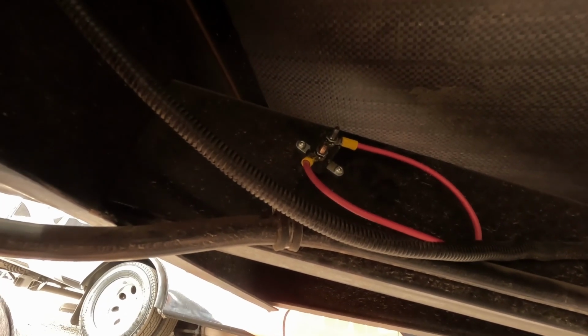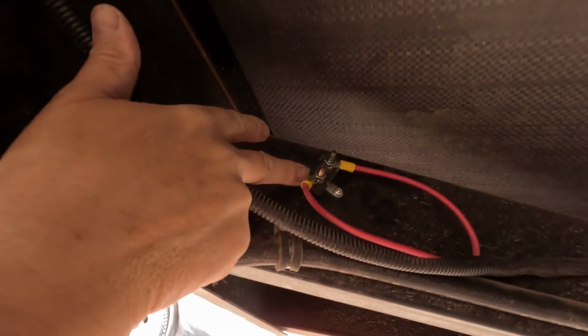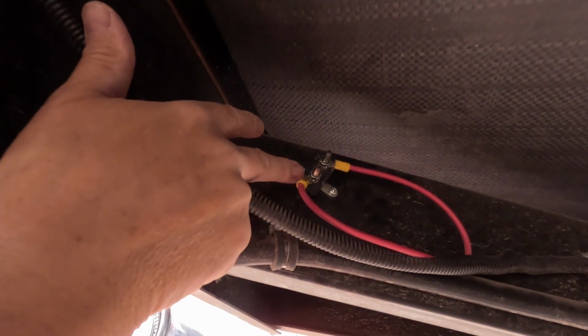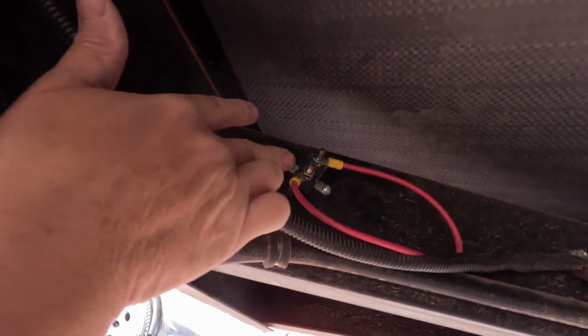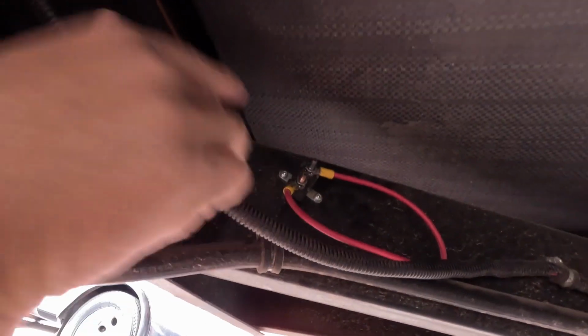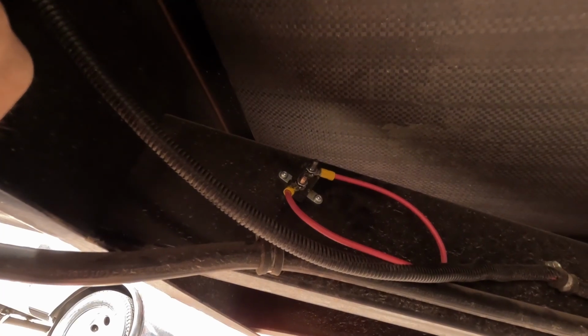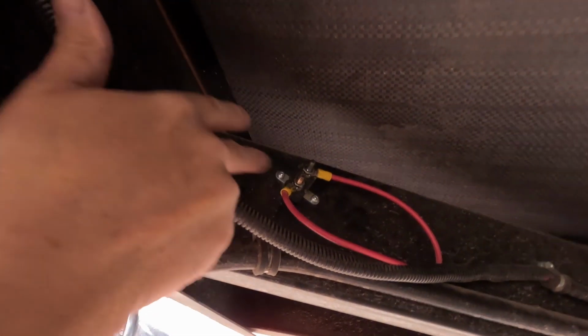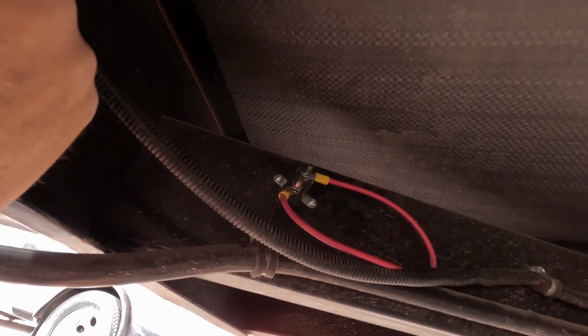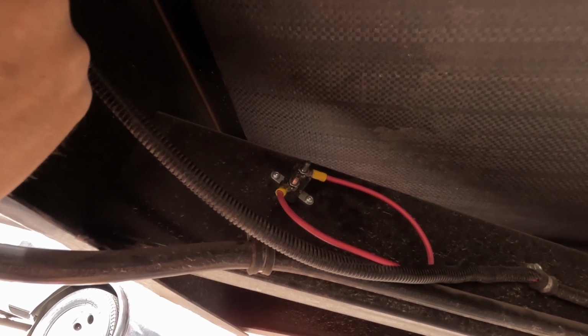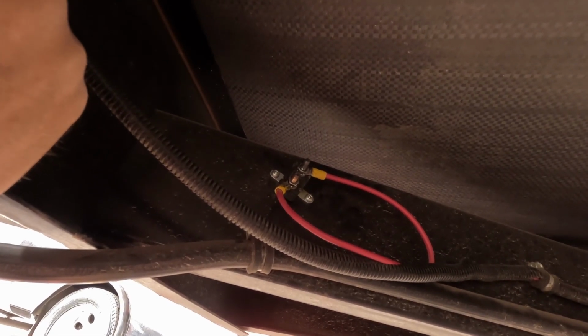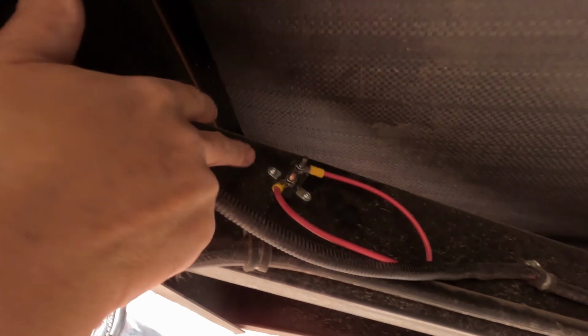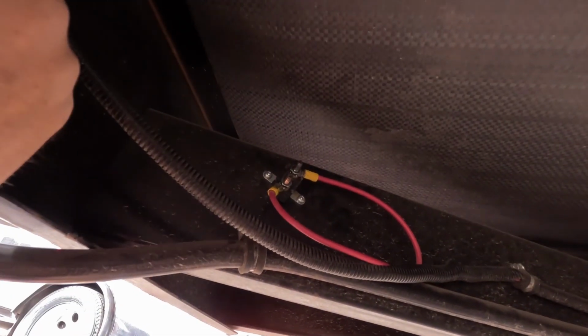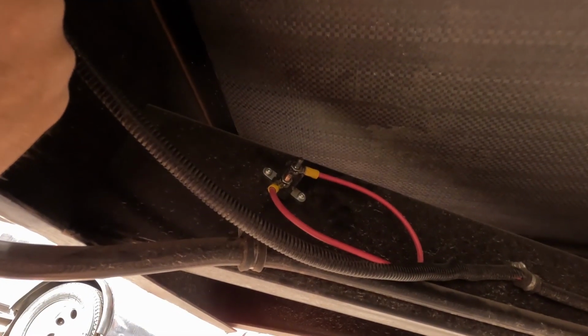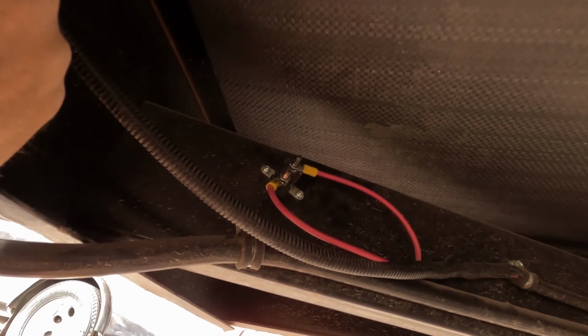There is a way that you can check these just to see if they're open or closed. You just want to check resistance between the two. But unless you put the voltage across it, it's not going to reset at a high enough voltage. So you have to put a high enough voltage across this to have it reset, and then it's just going to open and then close again.